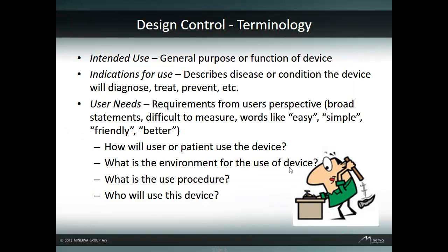Design control uses some specific terminology. Intended use is the stated general purpose or function of the device. Indication for use is the stated disease or condition that the device will diagnose, treat, prevent, etc. It is also a good practice to state the unintended use of the device.